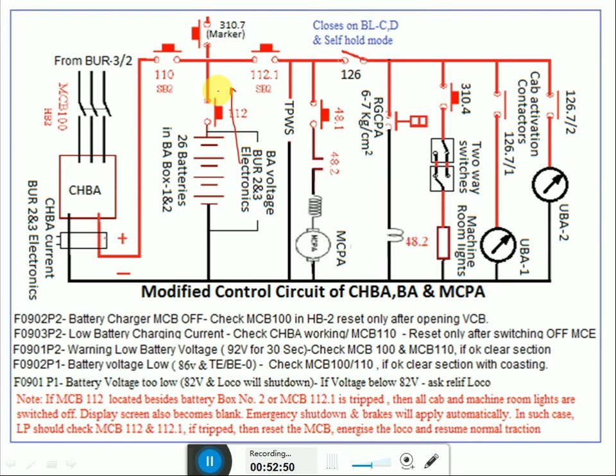If 112 trips while on run, in low energized condition, normal working can be done only at neutral sections, or whenever we trip the DJ. Then C switches off, control circuit supply is cut off, BP will drop and the train will stop. We can suspect breaker 112 was defective. We already discussed these problems in the battery and CHBA circuits in 3-phase locos.